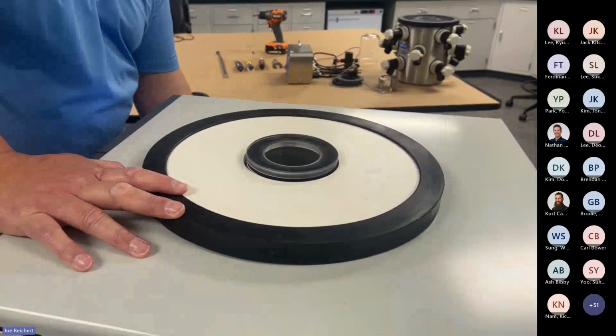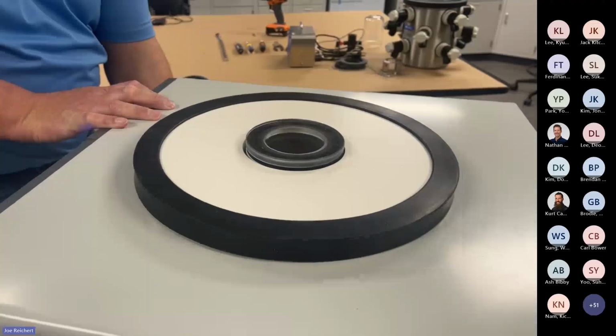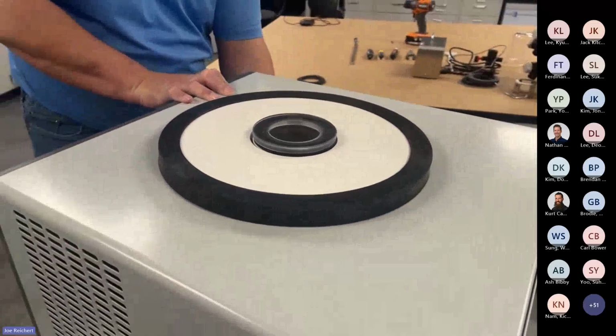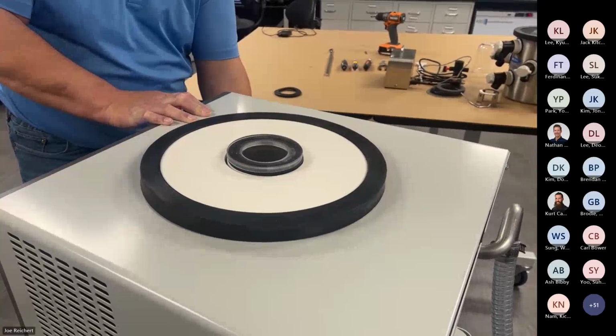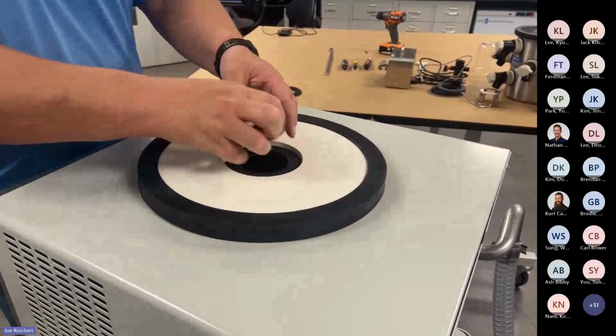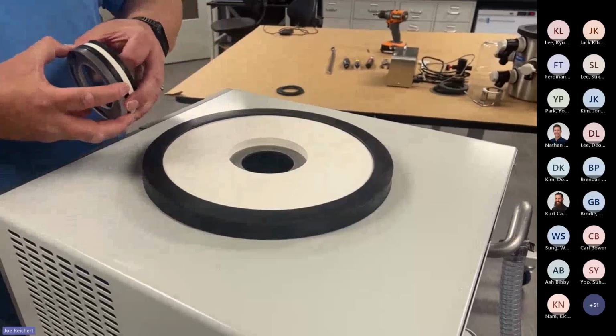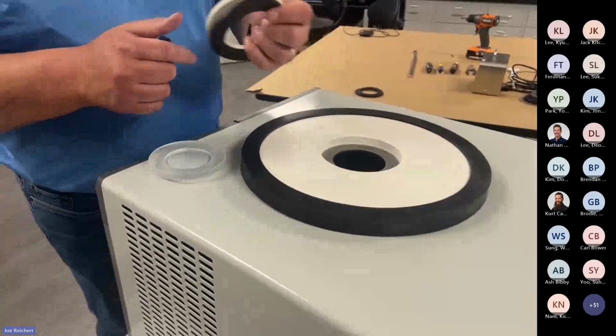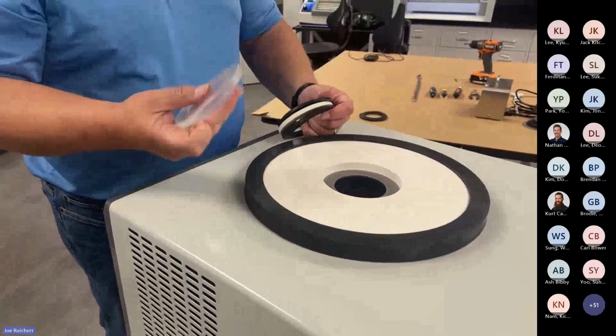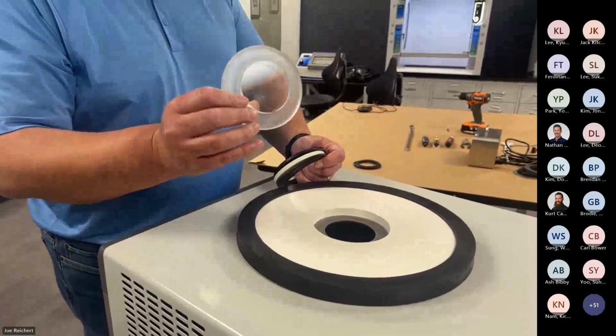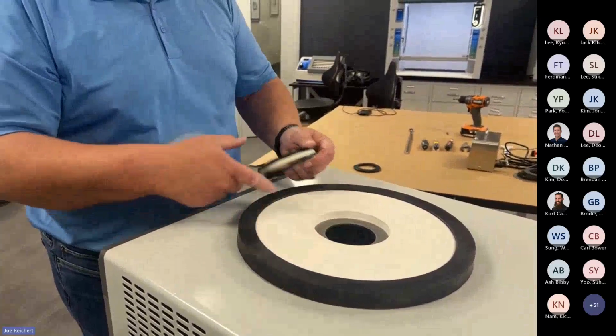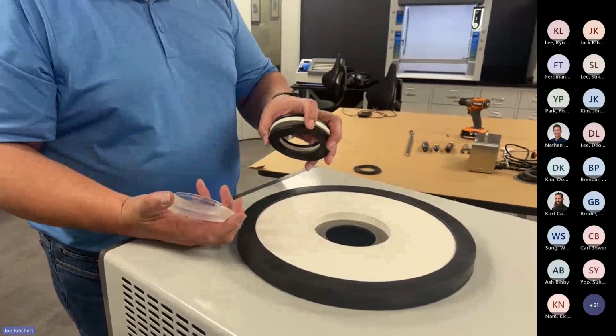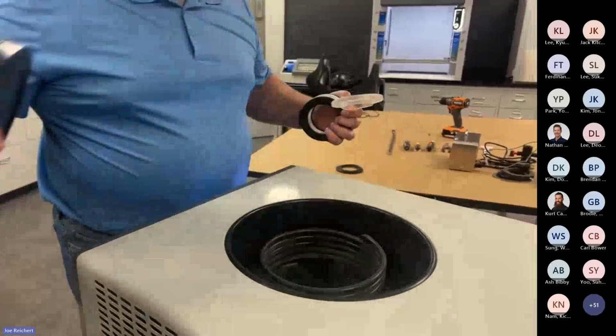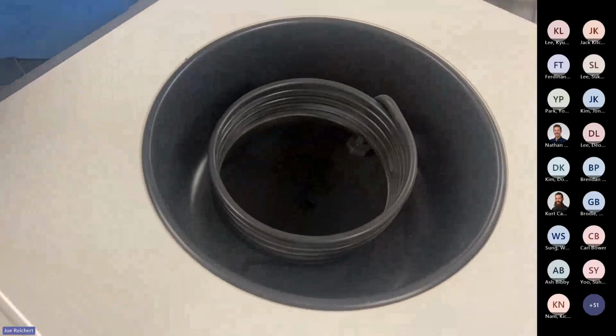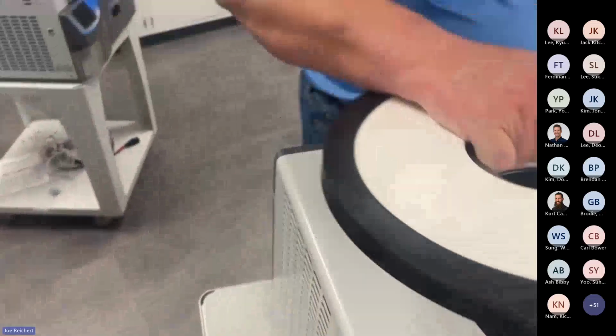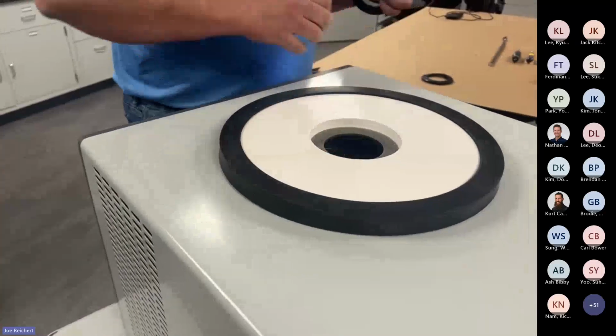So on the freeze dryer itself, I'm going to stop my vacuum. And all I have here for my leak testing is a couple of gaskets, a spacer that comes with your chamber, and then we have these little plugs as well. These work nice on covering up the top of the port. They can also work on consoles as well, covering up those. But inside the chamber, obviously you have just the coil. We have our steel lid that came with the unit. And we just cover up the top, make sure our gasket slides inside the top of the chamber.